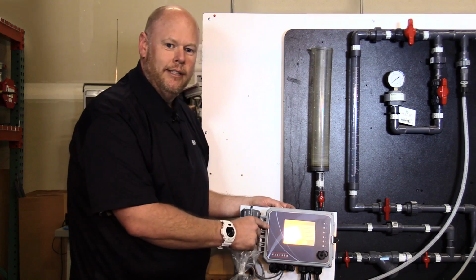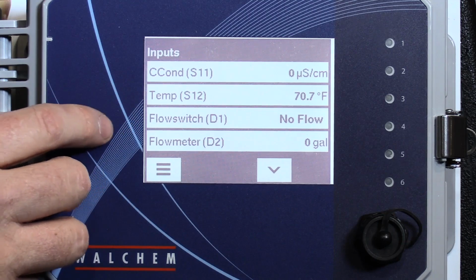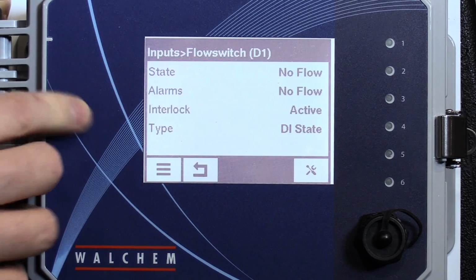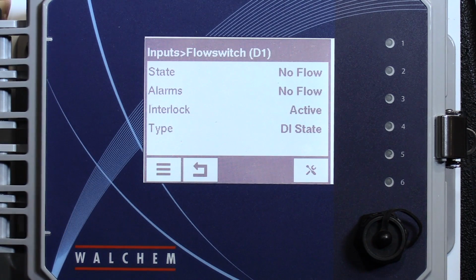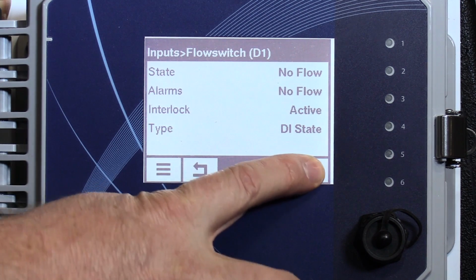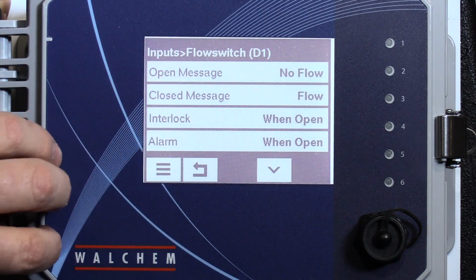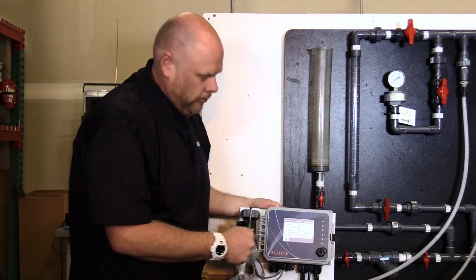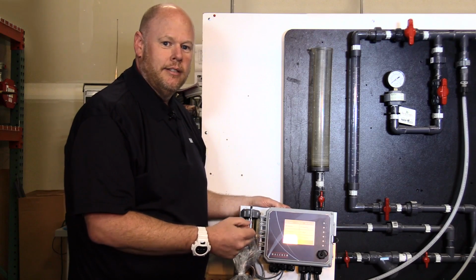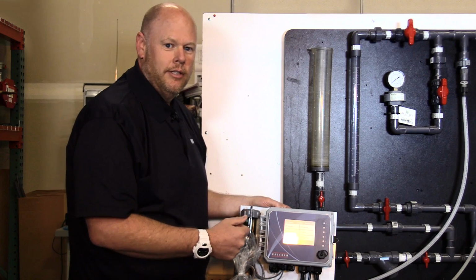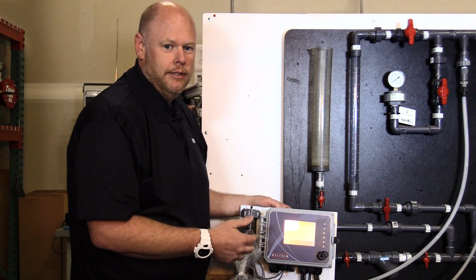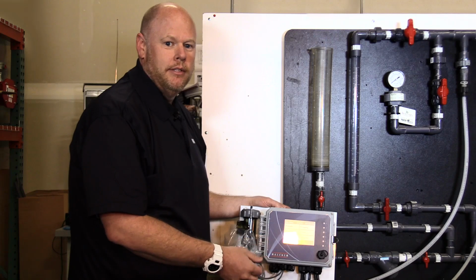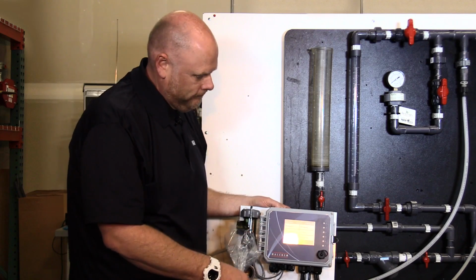Then we would go in and program the flow switch. Touch it there. When it's mounted on a panel, you don't have to change anything. If it was not mounted on a panel and you added, you would hit the tools button and you would add the flow switch into it. Once you've programmed the sensor and the flow switch, you would program the output. The outputs are the 6 pigtail relays on the bottom of the controller for either pumps and controls or valves.